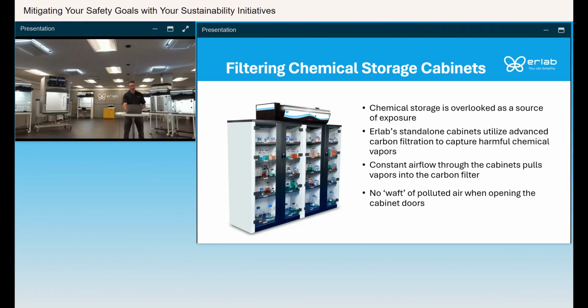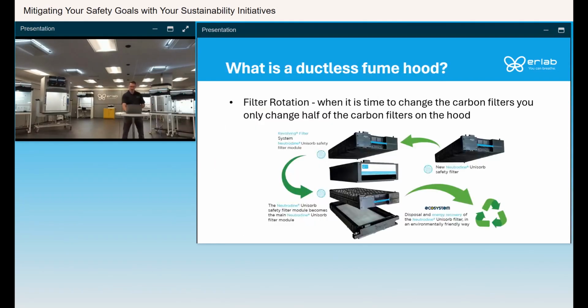And when it is time to change the filters, you're only going to change half the carbon filters on the hood. So ideally, it's a 2 to 4 year lifespan, depending on the size of the hood, whether it's 3 foot to 6 foot. And on that original picture I showed you with our ductless fume hood, that was a Captair 483 that had 3 filtration columns. So when you first start using that hood, you're going to have 6 carbon filters on the hood. Then ideally, every 2 years, you're going to change out 3 of the 6 carbon filters.